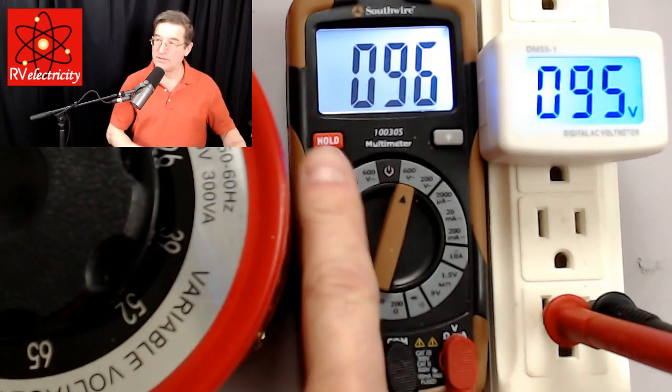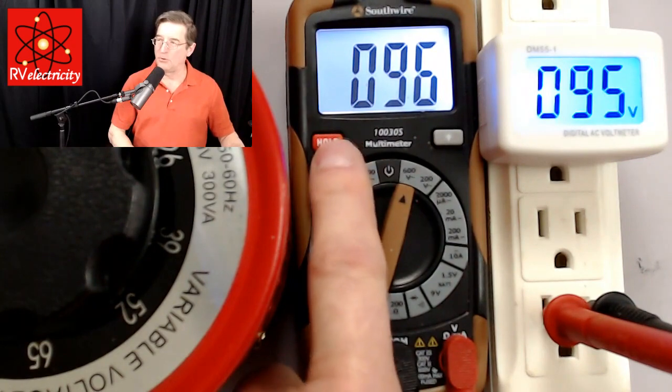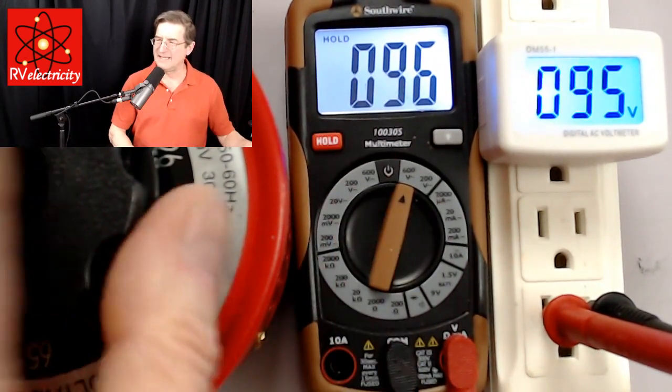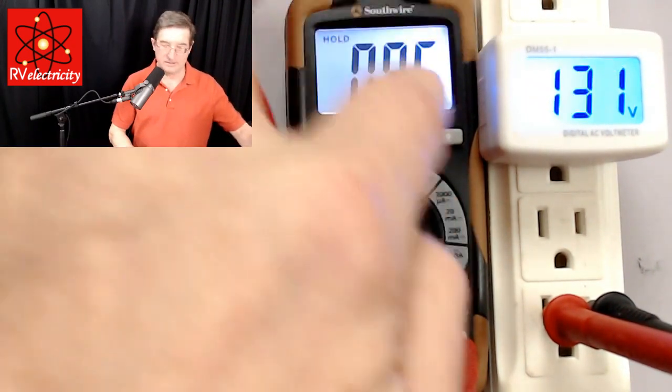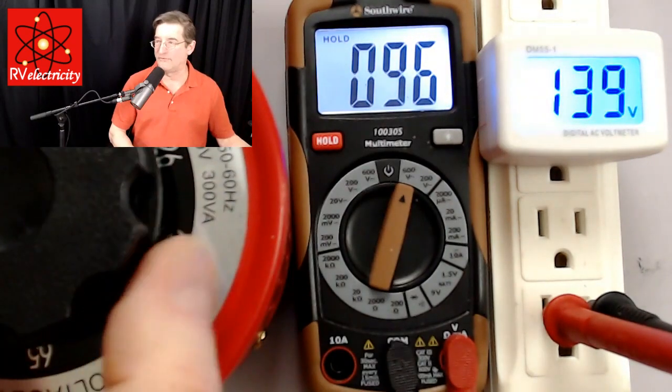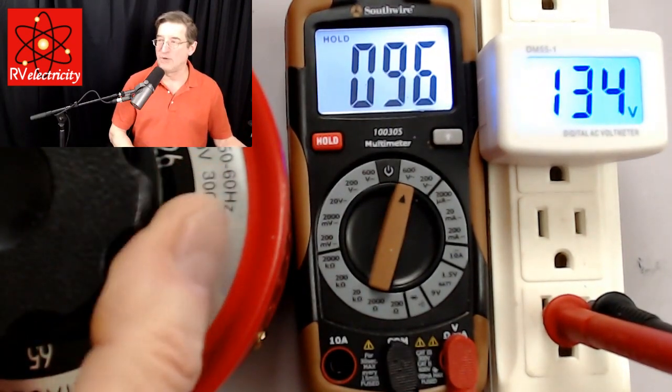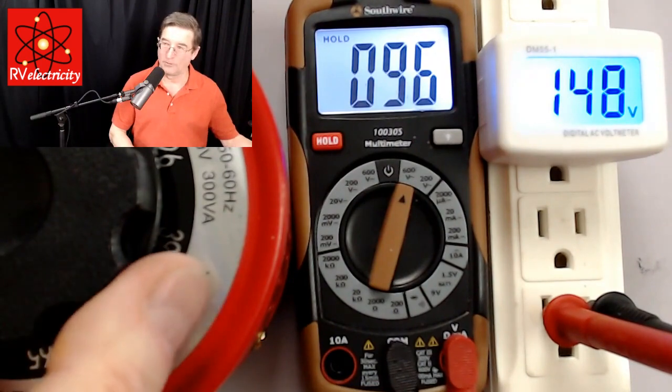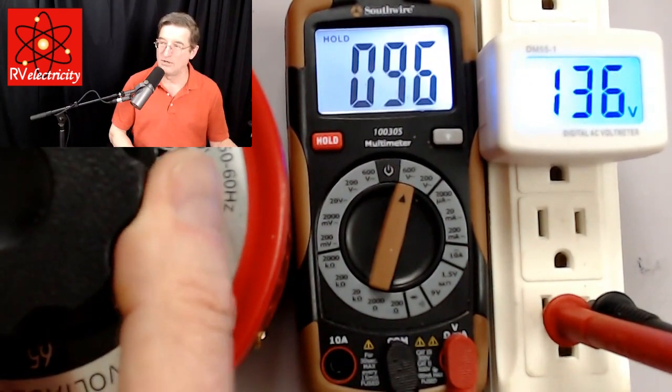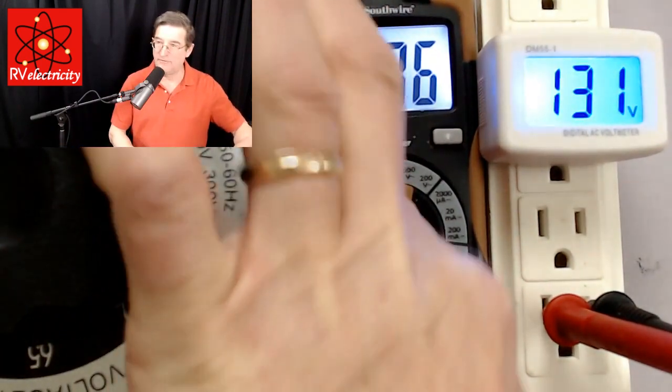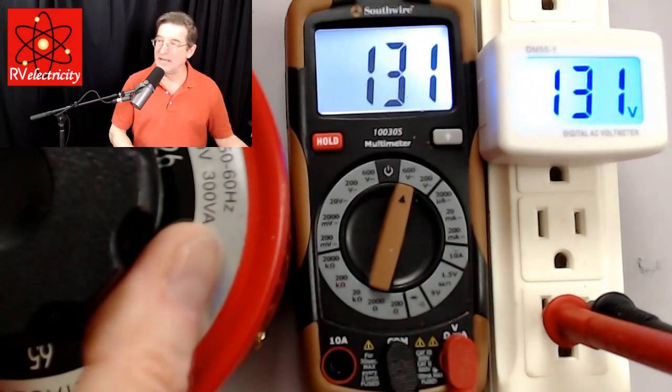Let me show you what this hold function does. When you push the hold function, it says hold and it kind of locks this meter reading in at whatever your last reading was. So you do not want to leave that engaged because you could be 140 volts, 150 volts in there and not know it. So always leave that little hold button disengaged.